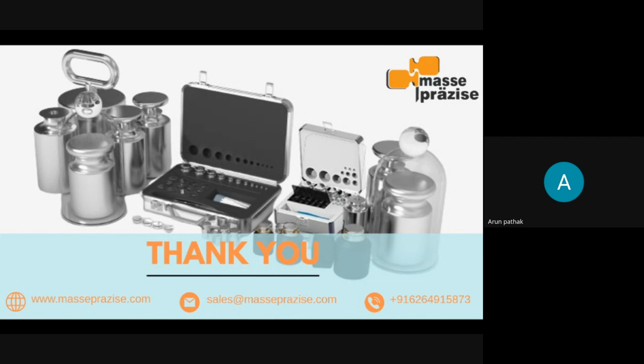For calibration laboratories, there is a guideline called NABL 129 that is only applicable to calibration laboratories. They can follow that guideline, and for others like pharma and other manufacturing, you can refer to that ILAC policy and from there find out what should be the calibration interval for your weights. In that policy, they basically ask to maintain quality check data, and until the data remains within the control limit, you can use that weight. Suppose you have quality checks of 5 years, and you found that the weight is not deviating from its nominal value more than the expected limits, then only you can go for the 5 year or 3 year validity. So I think that ILAC document will give you more clarity.